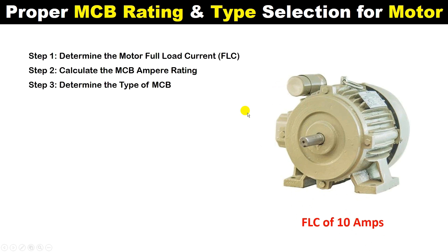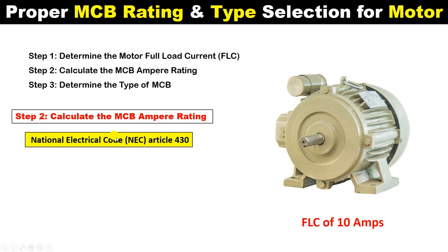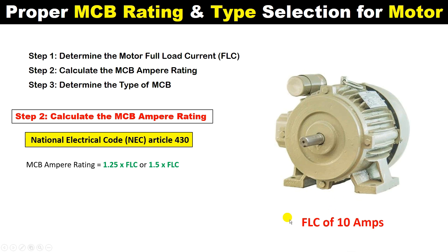Friends, for this motor, if you use an MCB, then how much rating MCB must be used — for this there is a rule. In Article 430 of the NEC it is stated that the rating of the MCB must be the FLC multiplied by 1.25, or if you want to add more protection then you can use 1.5 also. So the MCB rating must be 1.25 times the FLC.